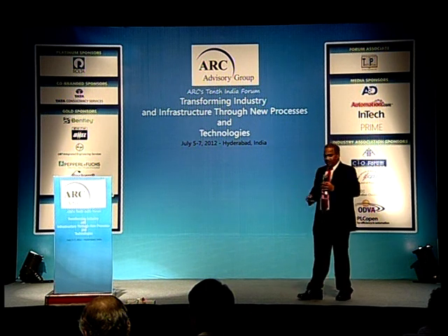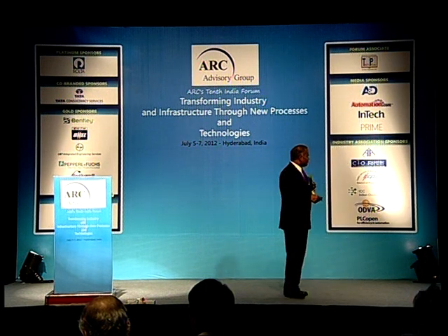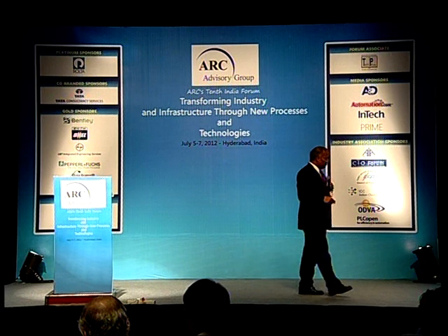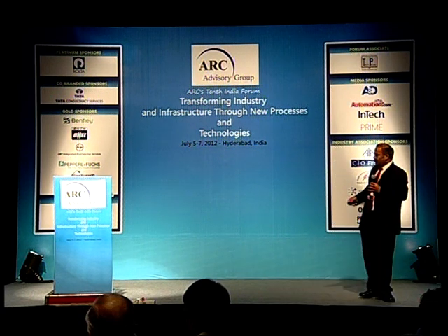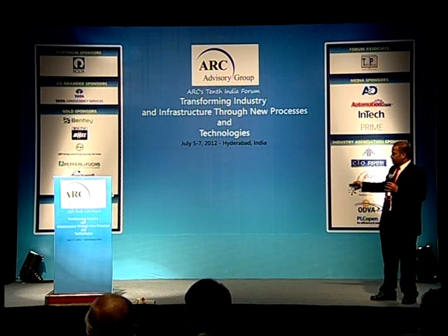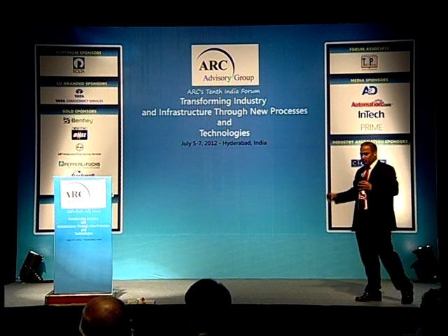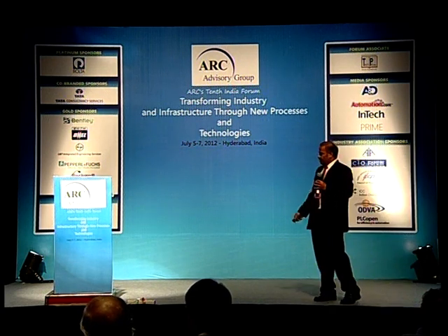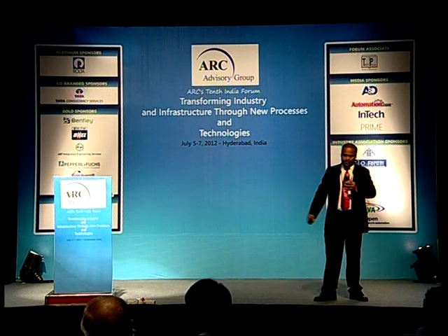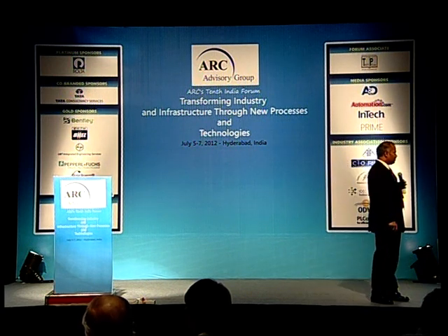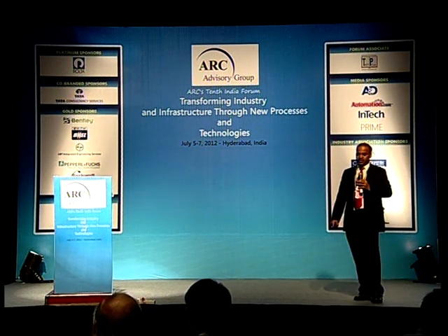The interesting factor here is that at the end of the day, the complete cost saving and time saving with the Fieldbus's built-in diagnostic can be done for 1,200 loops in less than 3 days, whereas in the normal conventional method, it takes almost 50 days. With Fieldbus, even without the built-in diagnostic, that reduces the time by half.